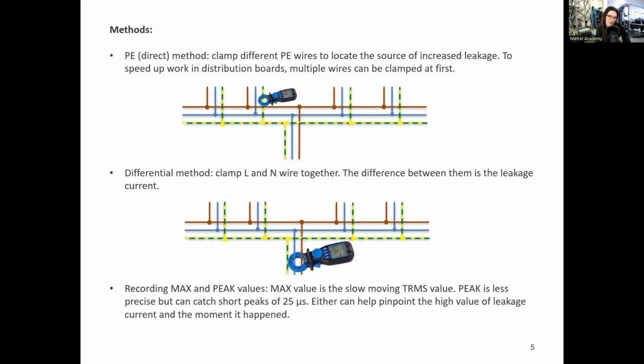This is the differential method, where we clamp the line and neutral wires together. The difference between them is the leakage current, and this method takes into account the whole difference, so even the current that might have run away from the local protective earth wire. However, this method has a mild disadvantage. In this case, we are looking at a very small difference between two relatively large currents that are normally flowing in the line and the neutral wires. So the clamps must be particularly well shielded and a well executed measurement instrument to be able to reliably sense this difference. The MD9273 is absolutely up to this task.